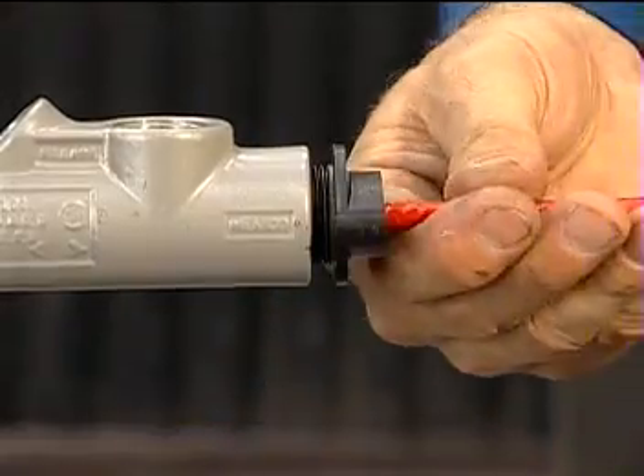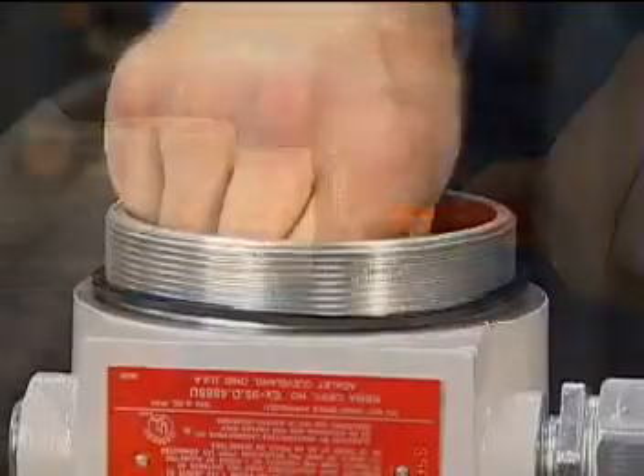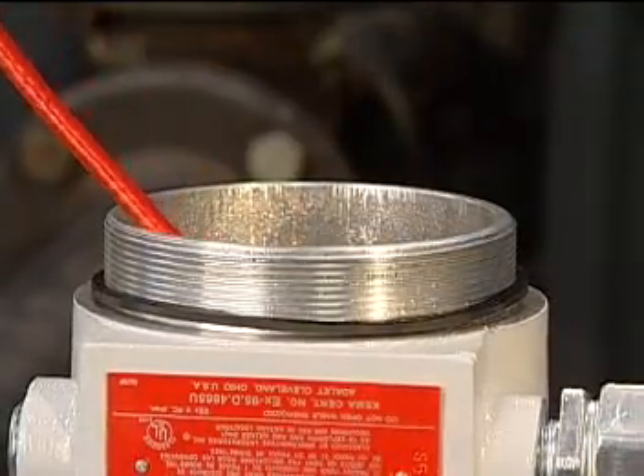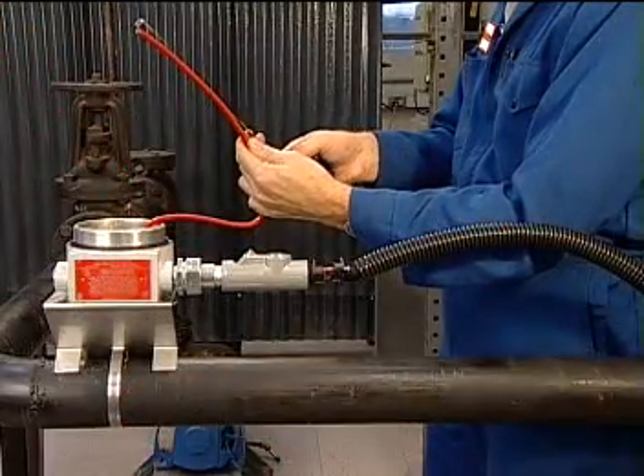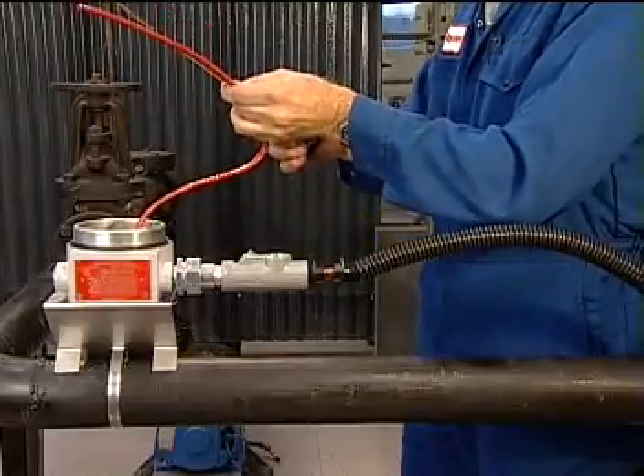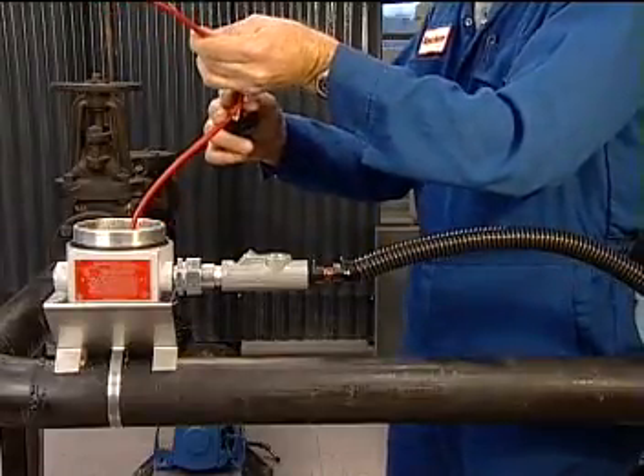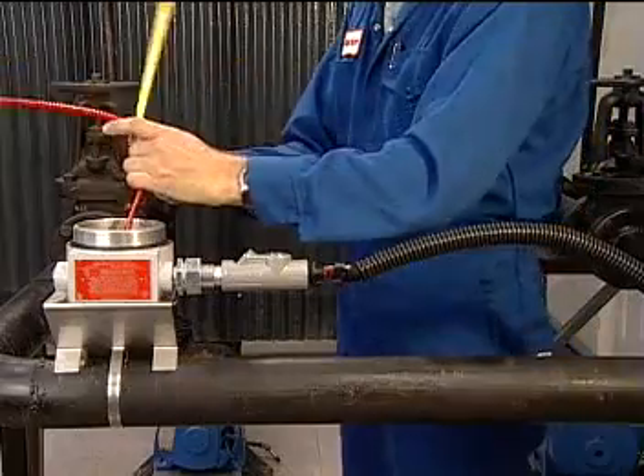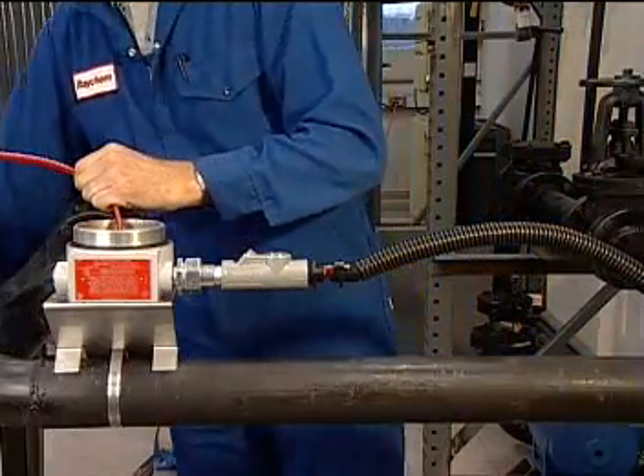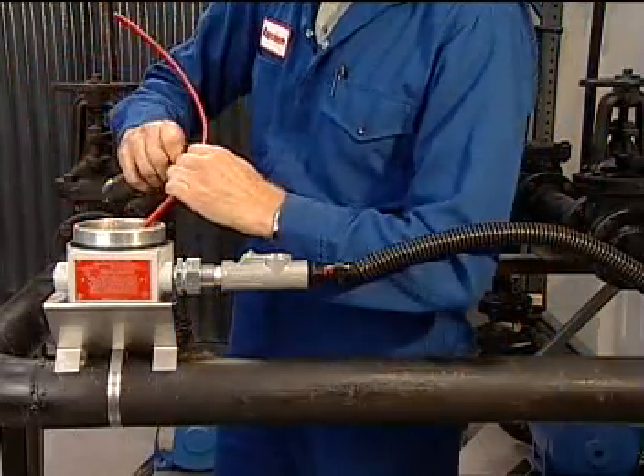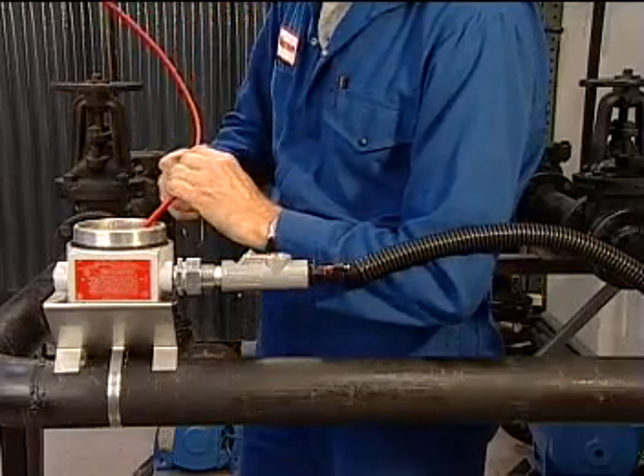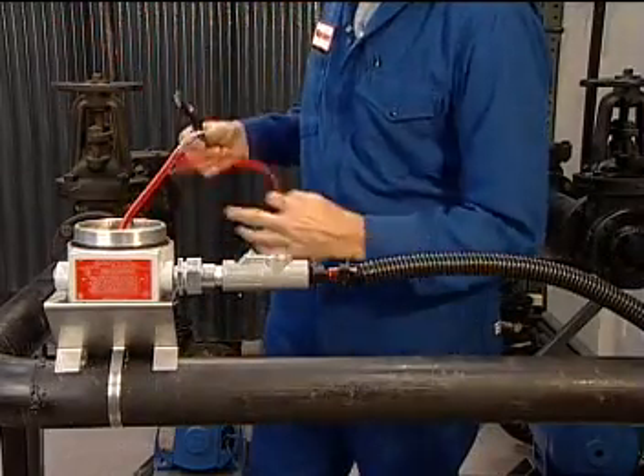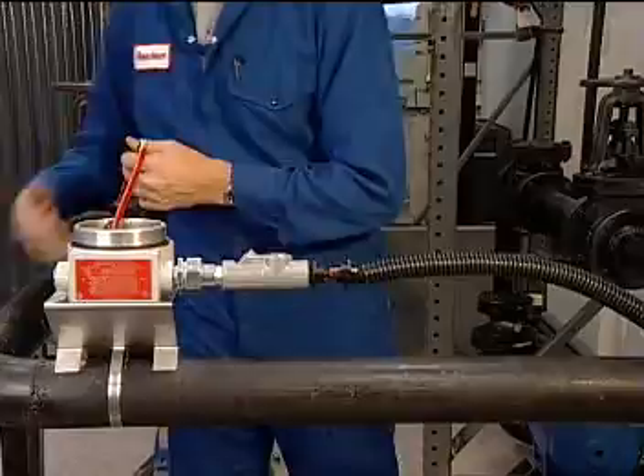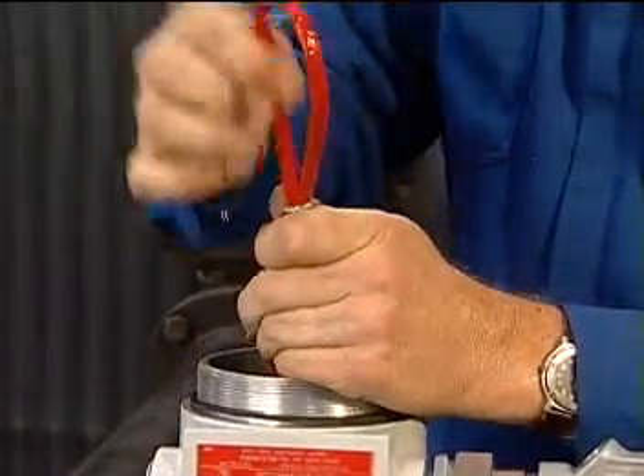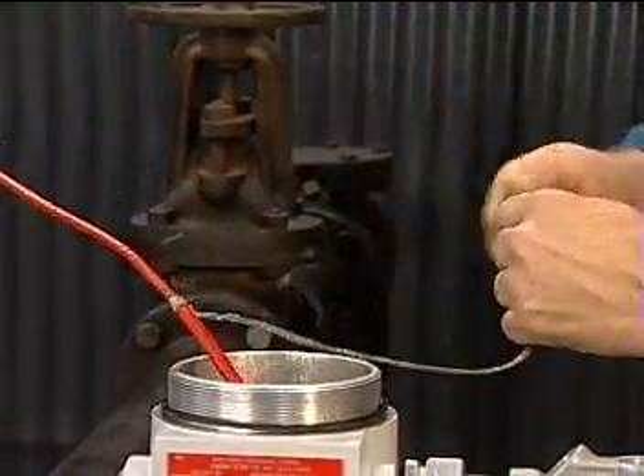Slide the cable through the sealing fitting and box so that it extends 20 inches beyond the box. Strip the cable using the appropriate cutback dimensions for the style of core insulator you use. If a heat shrink core insulator is used, follow the specific steps in the installation instructions. In this example, the cold-applied core insulator will be used. Strip the outer jacket of the cable back 14.5 inches. Then, pigtail the braid using the same method as for standard components.